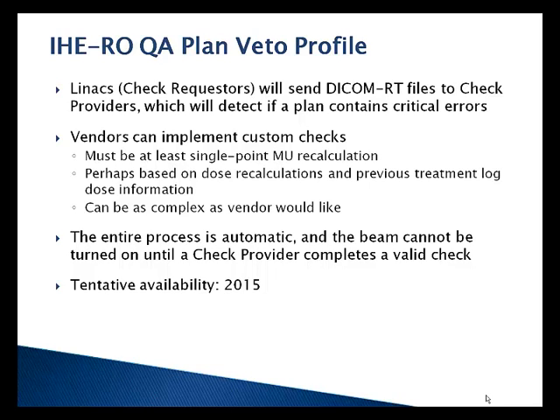The ABR also read the New York Times, and they came up with something they called the IHE-RO QA Plan Veto Profile, a very sexy name. Basically, in a couple years, what we'll be doing is before your Linac turns the beam on, it's going to ship that DICOM-RT plan that it has in its possession off to a plan veto server. So the Linac is called a check requester. The plan veto server will be called a check provider. And the check provider's job is to detect if there are any critical errors there.